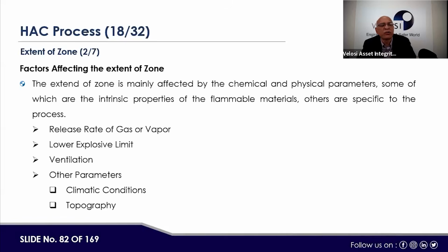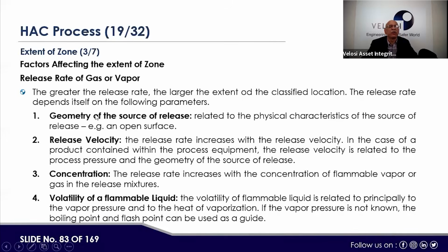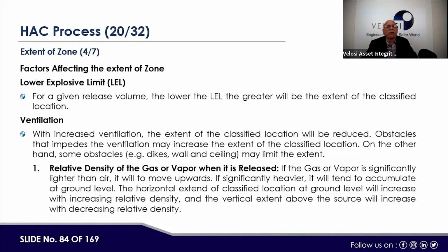Then the factors affecting the extent of zone are the release rate of a gas or vapor, lower explosive limits, ventilation, and other parameters like climatic conditions and topography. Other factors affecting the extent of zones are, for example, the geometry of the source of release, velocity, concentration, and volatility of the flammable liquid. This is also important: how fast and how long it will take for the released material to make a dangerous, basically explosive, mixture. Similarly, the lower explosive limit of that particular fluid is also important. What kind of ventilation is there? That ventilation can also help to disperse the hydrocarbon released from that particular point source.